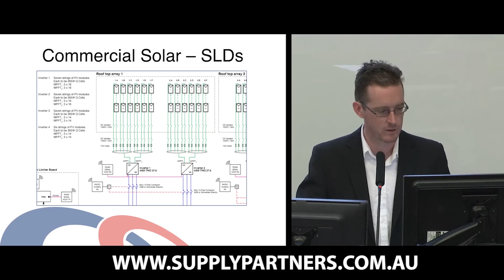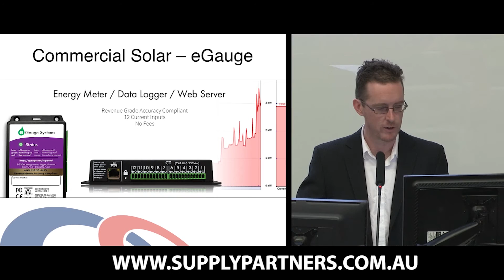Quick comment on the E-gauge. It is an interesting piece of kit. Class 1 accuracy and 12 CT inputs, which means that on a 3-phase project, you can monitor the site load as well as the inverter performance, and then, say, 2 other sub-circuits. On a single phase, you could be doing as many as 12 circuits.